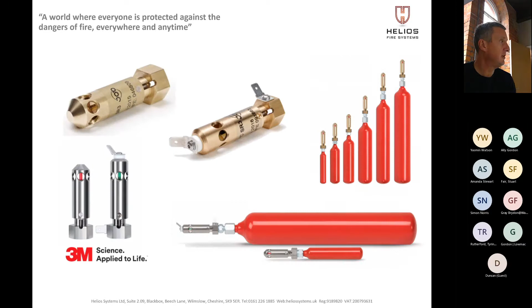So when we're actually installing, this would be a typical installation. When we do this for a client, we take all the client's cabinets, we do a full design for them to show the areas, take the full volume. We have to work the volume of the area out, even if there is no compartmentalization between cabinets. So we can work out what volume is in this cylinder that will protect that entire area from a potential fire.